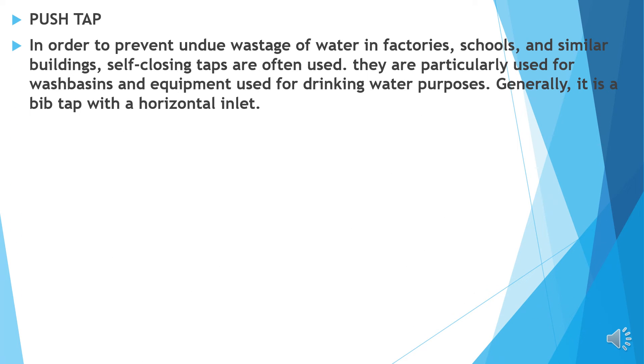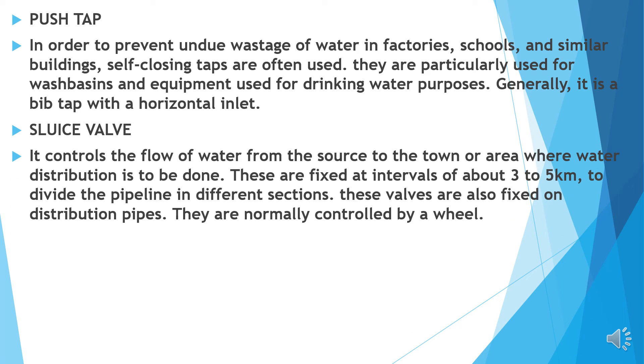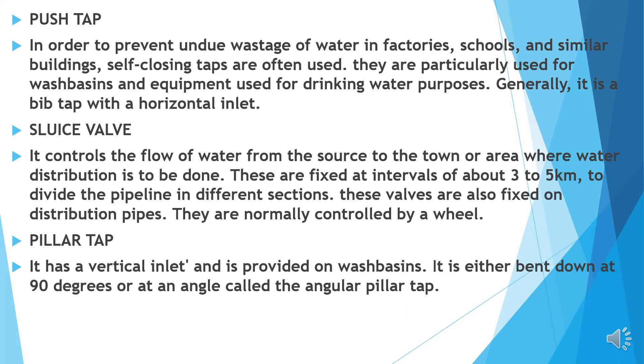Push tap: in order to prevent undue wastage of water in factories, schools and similar buildings, self-closing taps are often used. They are particularly used for washbasins and equipment used for drinking water. Generally it is a bib tap with a horizontal inlet. Sluice valve: controls the flow of water from the source to the town or area when water distribution is done. Fixed at intervals of 3 to 5 km to divide the pipeline in different sections; also fixed on distribution pipes and normally controlled by a wheel. Pillar tap: it has a vertical inlet and is provided on washbasins. It is either bent down at 90 degrees or at an angle, called an angular pillar tap.